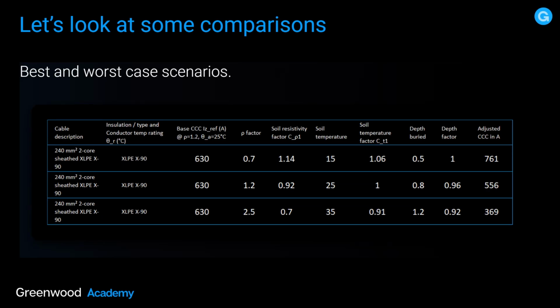So in the first row, under the heading, you're looking at the same base. You're looking at a P factor of 0.7. You're looking at a soil temperature of 15 and a depth of bury at 0.5. So that cable can cope with 761 amps. So if we go to the next option with a thermal resistivity of 1.2, and a 25 degree soil temperature and a 800 mil bury depth, 556 amps, all good. Let's go to the last one.